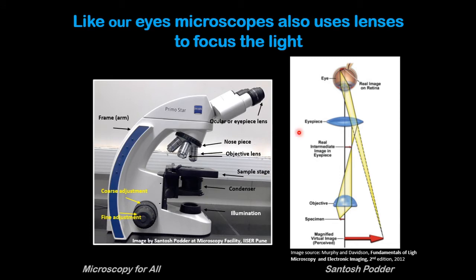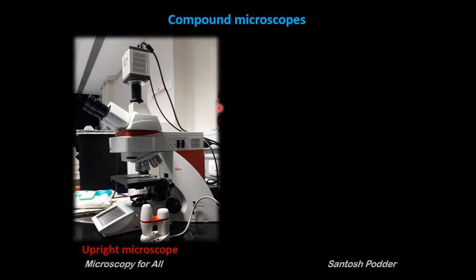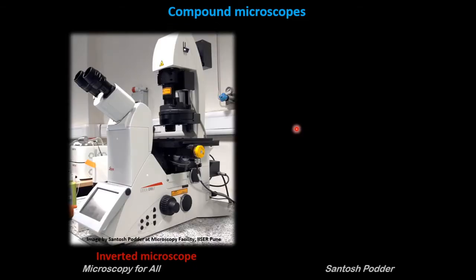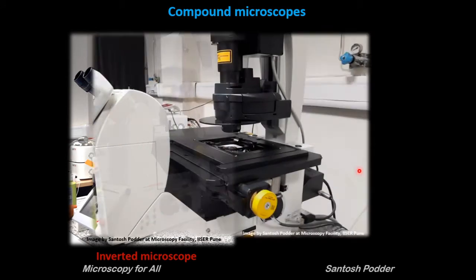Compound microscopes are so called because they are designed with a compound lens system. The objective lens provides the primary magnification, which is compounded or multiplied by the ocular lens or eyepiece. Compound microscopes can be loaded with several objectives for magnifications ranging from 5x to 100x. Eyepieces are generally 10x, resulting in a total magnification of 50x to 1000x. Compound microscopes may be upright, where objectives are above the sample stage, or inverted, where objectives are below the sample stage.